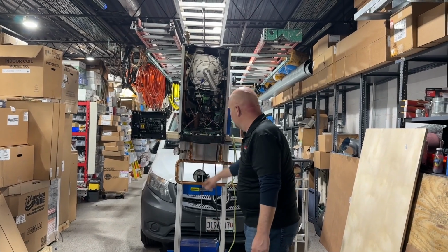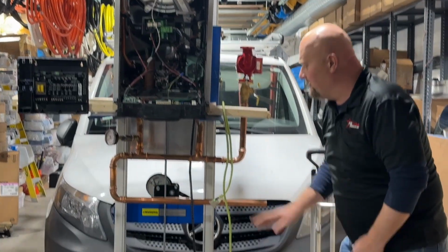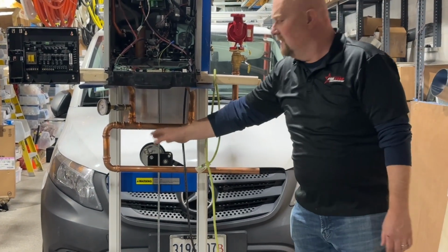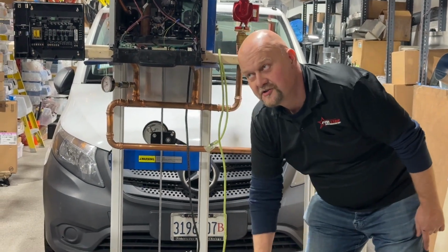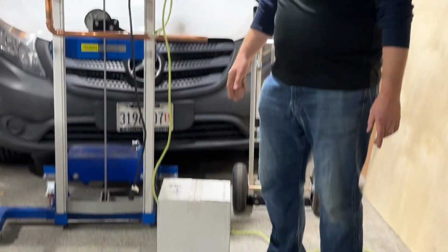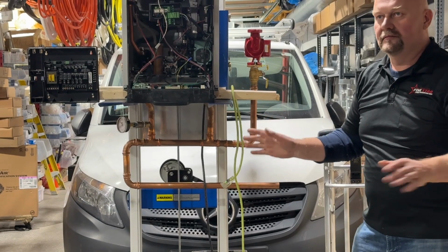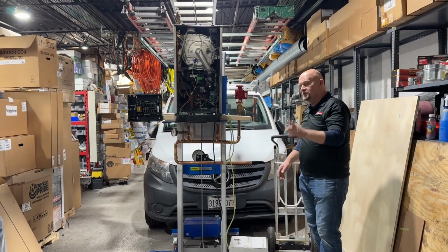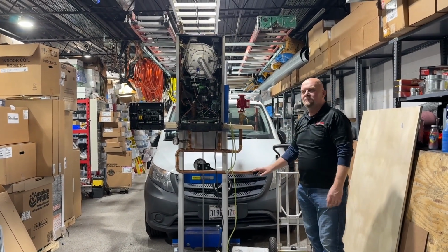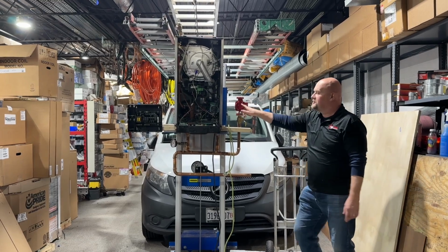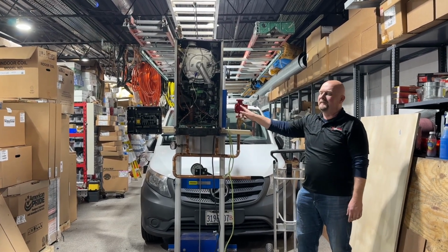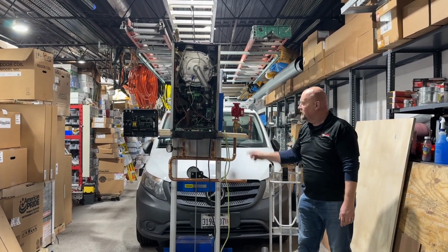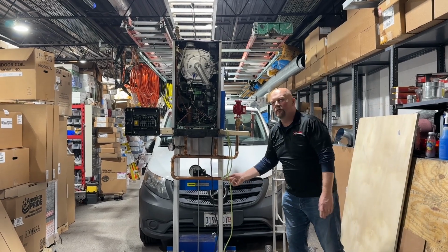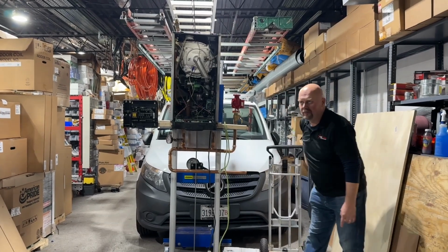So that's just piping. Also, along with this, every boiler is going to have a water feeder, a gauge, and a pressure tank to maintain the pressure. The pump could be on the supply or the return. Good question. Yes, the pump could be on the supply or on the return as long as the direction of flow is correct. So if you have this pump sitting here, then this arrow cannot point to the boiler, it has to be away from the boiler.